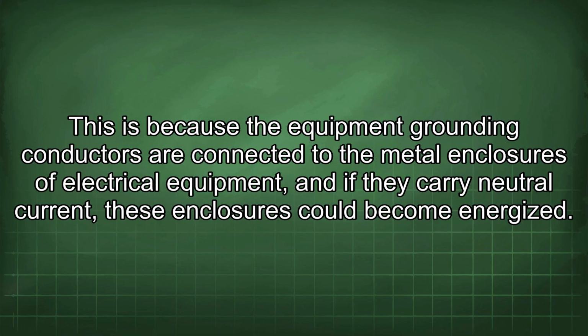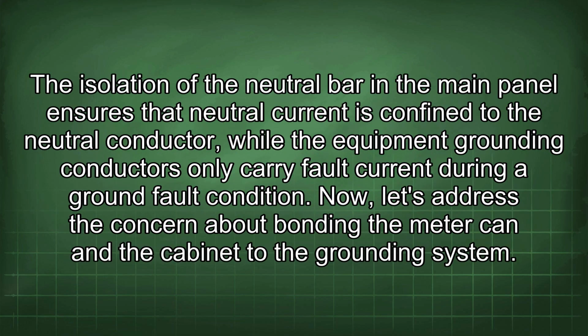This is because the equipment grounding conductors are connected to the metal enclosures of electrical equipment, and if they carry neutral current, these enclosures could become energized. The isolation of the neutral bar in the main panel ensures that neutral current is confined to the neutral conductor, while the equipment grounding conductors only carry fault current during a ground fault condition.